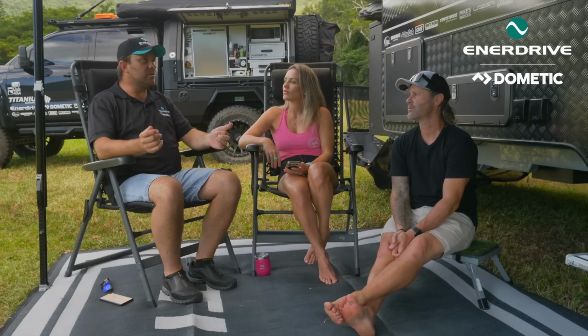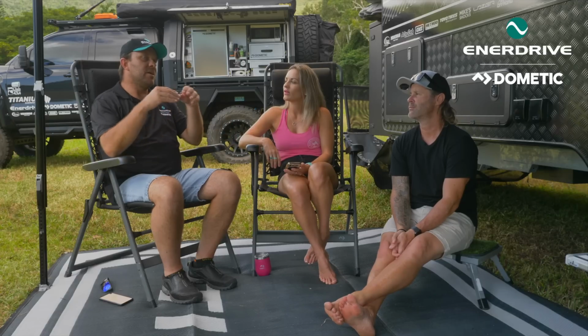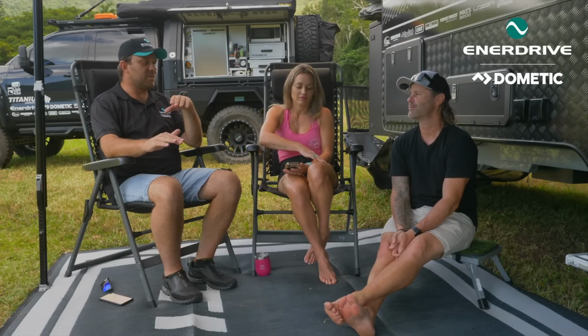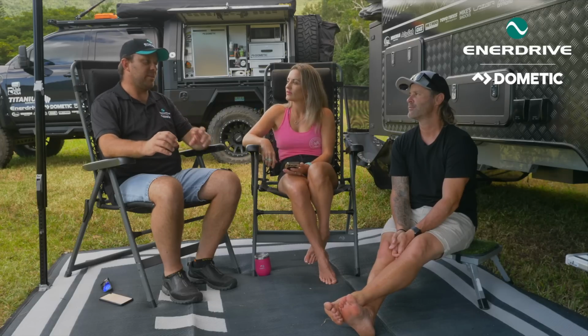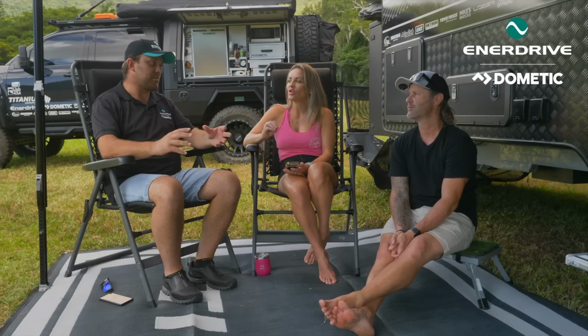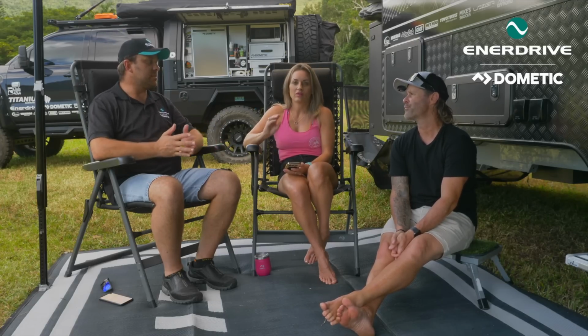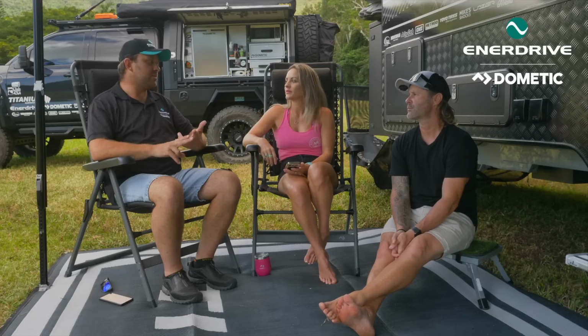Now, the fallacy there is a lot of people misunderstand that statement. You can use 100% of the power, but it's not good for the battery - in fact, it's stifling on the battery. It's a horrible thing to do to a lead-acid battery. So we're not talking about lithium batteries now? No, we're talking lead acid - whether it's AGM, flooded, or calcium, it's irrelevant.